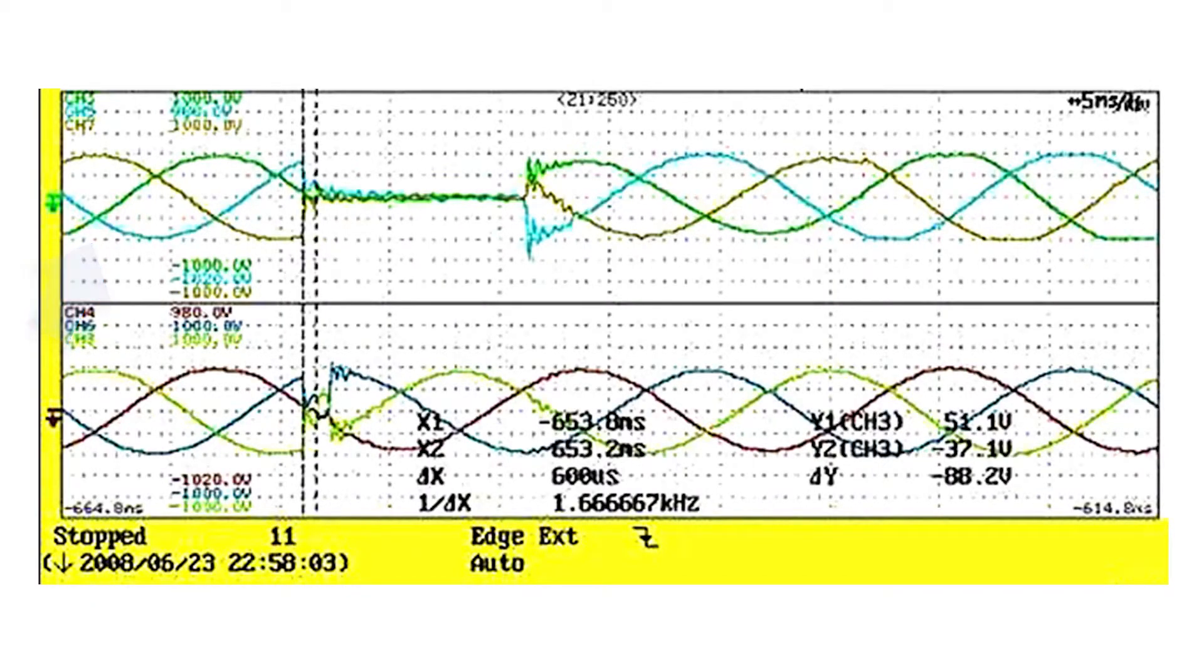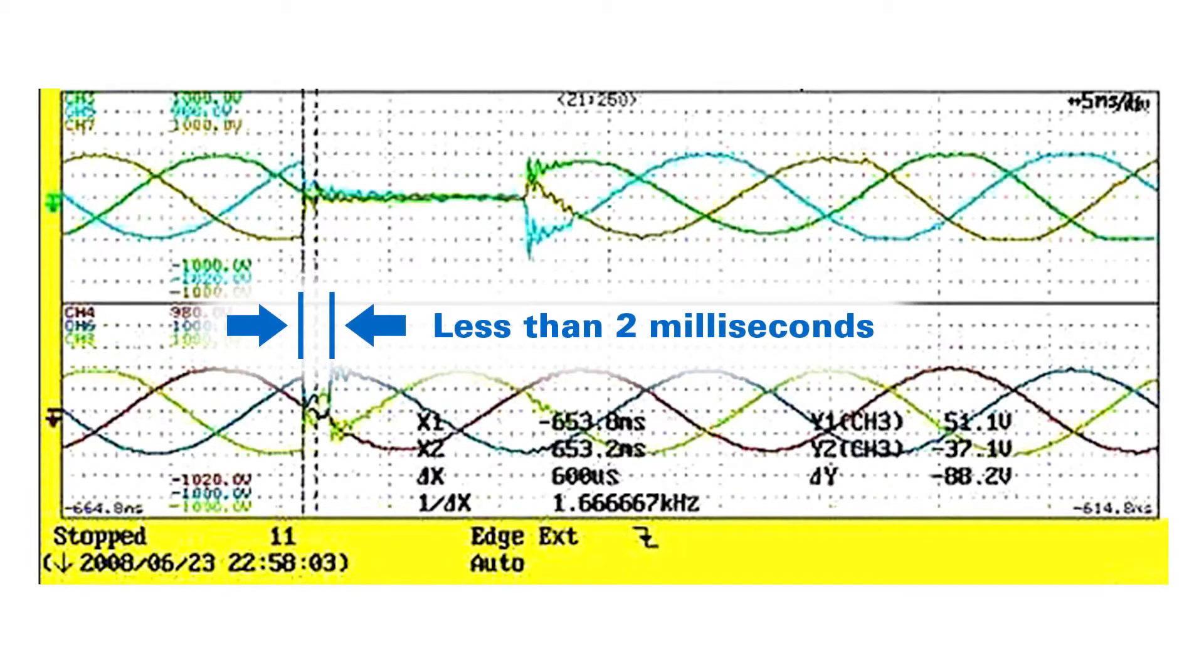Here we see the input power disrupted coming into the UPS and the output power here. At the same point, we do not go to zero volts but continue to produce a three-phase output. And the transition time from utility power to inverter power is in fact less than two milliseconds.